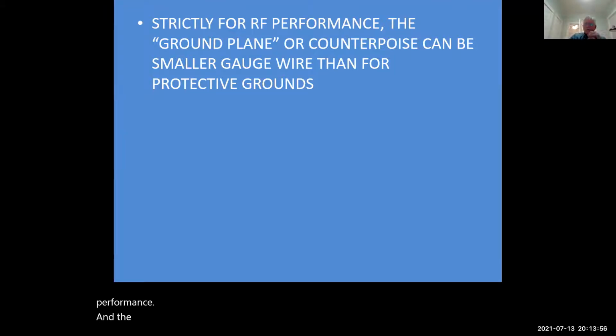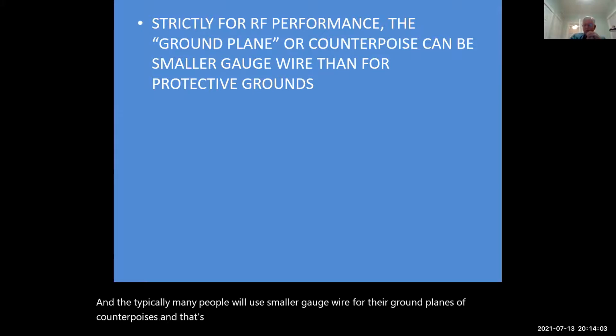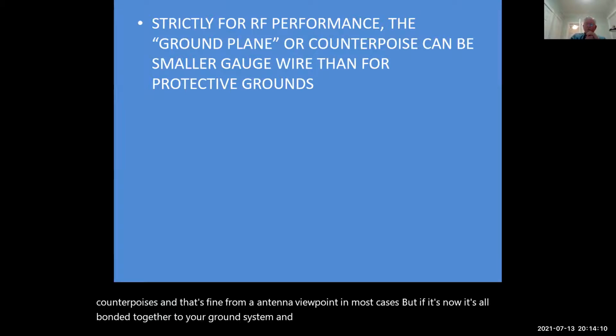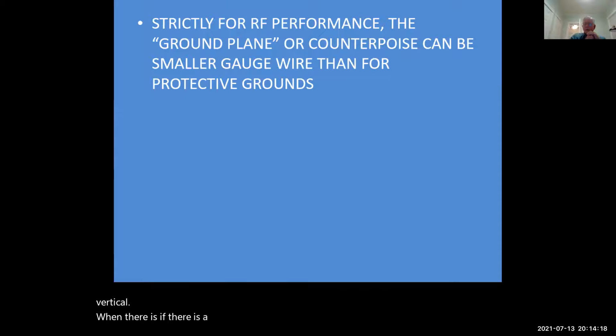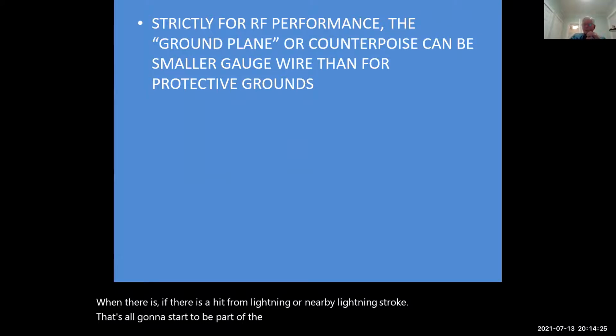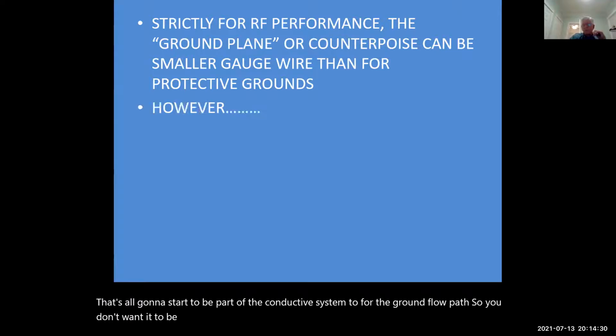Typically, many people will use smaller gauge wire for their ground planes or counterpoises, and that's fine from an antenna viewpoint in most cases. But if it's all bonded together to your ground system, and it's coming down from a tower or a very tall vertical, if there is a hit from lightning or a nearby lightning stroke, that's all going to start to be part of the conductive system for the ground fault path. So you don't want it to be small enough that it's going to burn up.